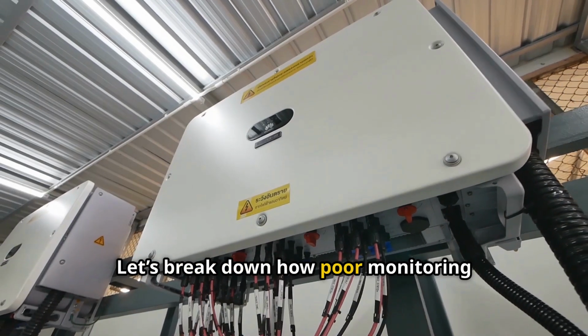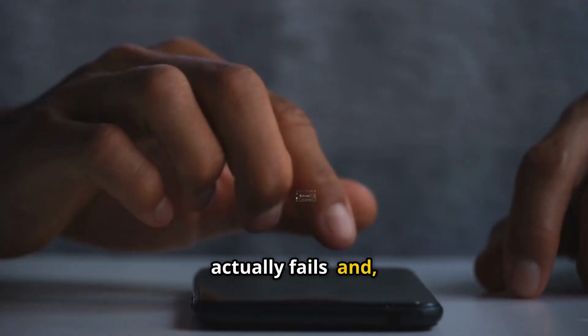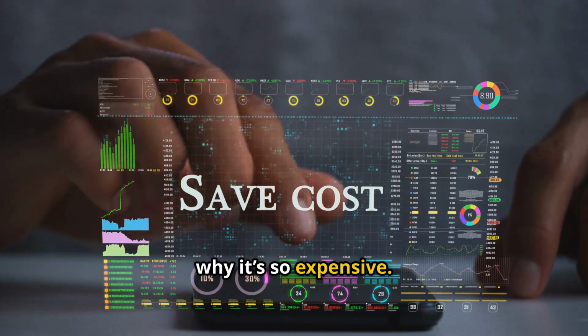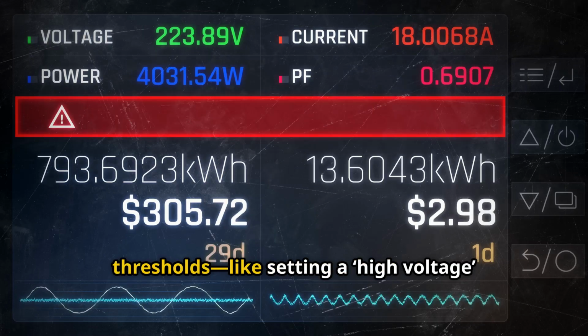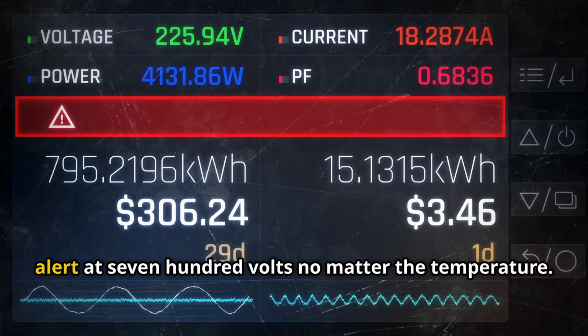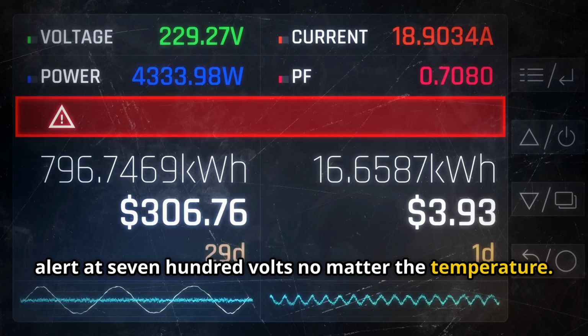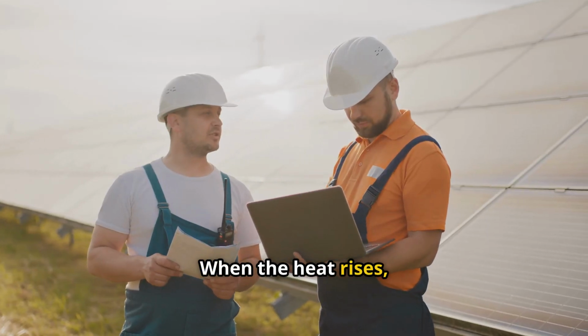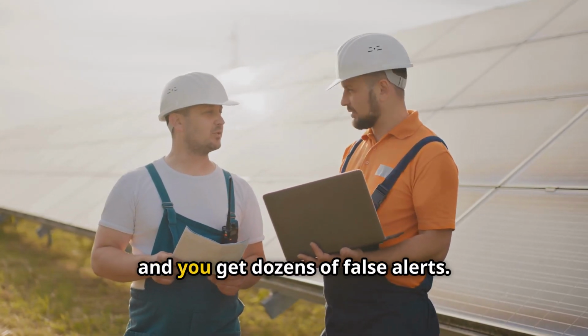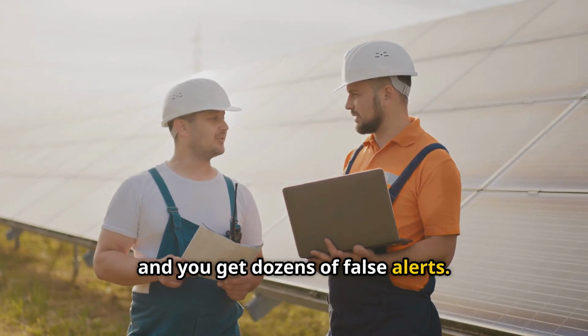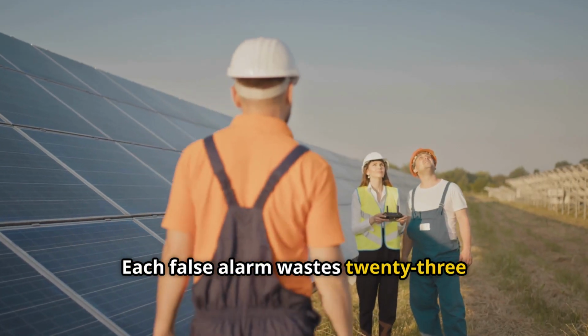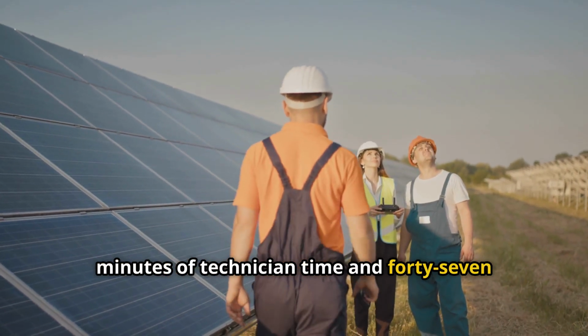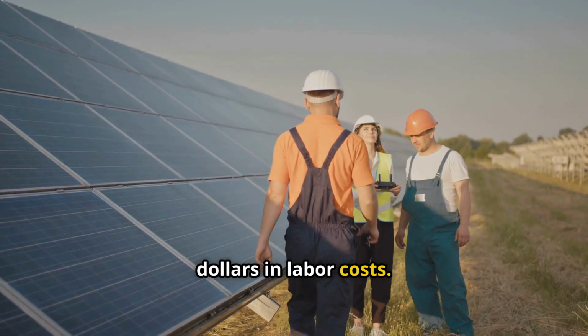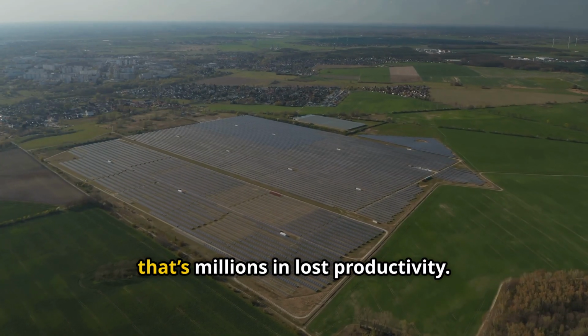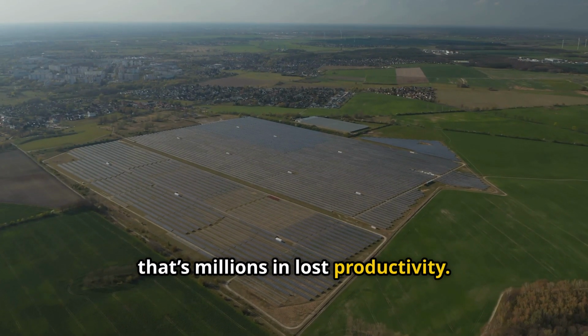Let's break down how poor monitoring actually fails, and really why it's so expensive. Traditional systems use fixed thresholds, like setting a high voltage alert at 700 volts no matter the temperature. When the heat rises, voltage naturally dips, and you get dozens of false alerts. Each false alarm wastes 23 minutes of technician time and $47 in labor costs. Across thousands of alerts, that's millions in lost productivity.